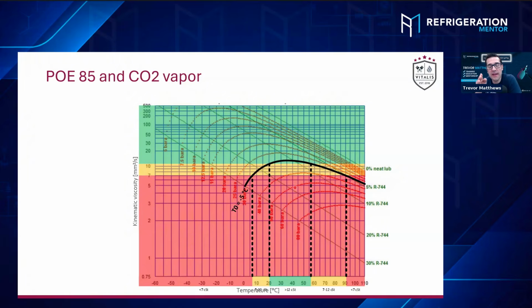So this is why you're saying that as the pressure goes up, the viscosity starts to drop. Temperature would be one. What else, is pressure the other one? Yeah, as the pressure goes up, it's the same as a bottle of sparkling water. It's closed, you have a high pressure, so the CO2 is dissolved inside the water. As soon as you open the bottle, you drop the pressure and it starts to gas out of the water. Here it's the oil. It's the same effect. So the higher the suction pressure gets, the more CO2 gets saturated in the oil. So the viscosity drops. The temperature is one part.